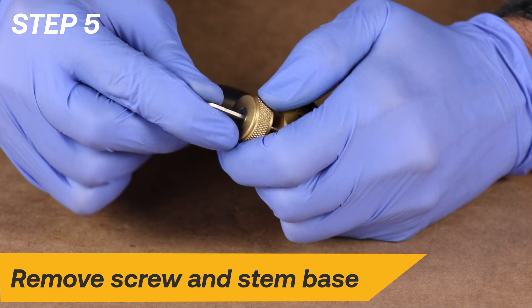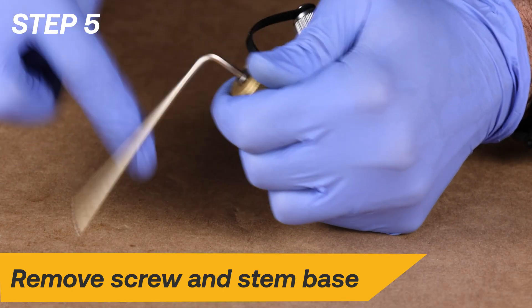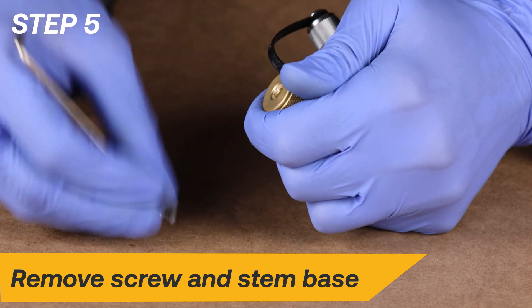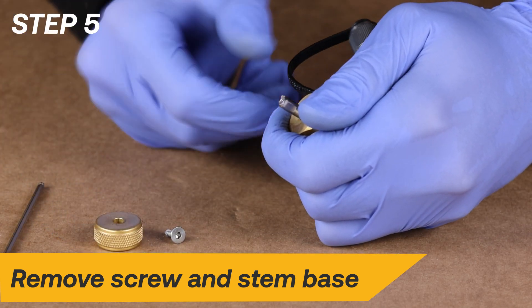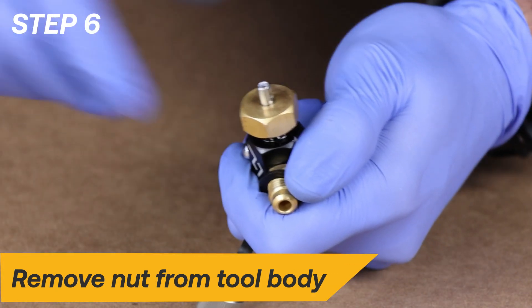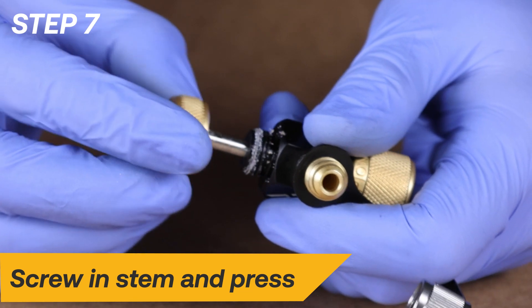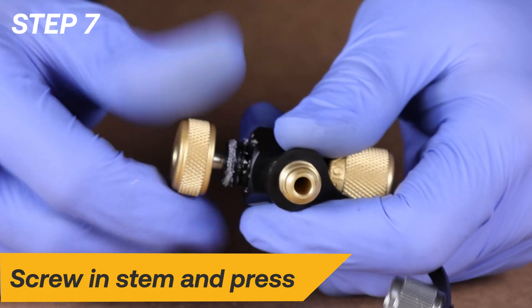To replace the stem assembly O-rings, first remove the screw and stem base from the stem with a 2.5mm hex wrench. Next, remove the nut from the tool body using two ¾-inch wrenches. Place the stem base back on the stem and turn the stem clockwise until the stem threads engage with the tool body.